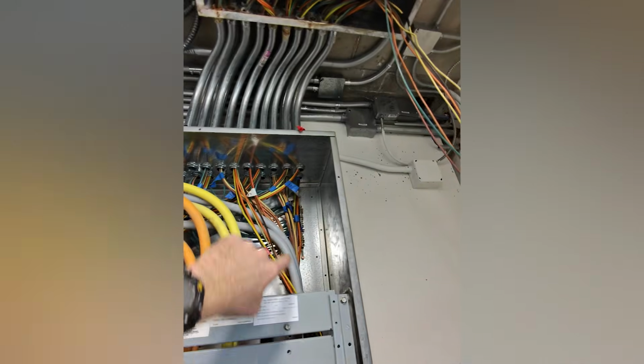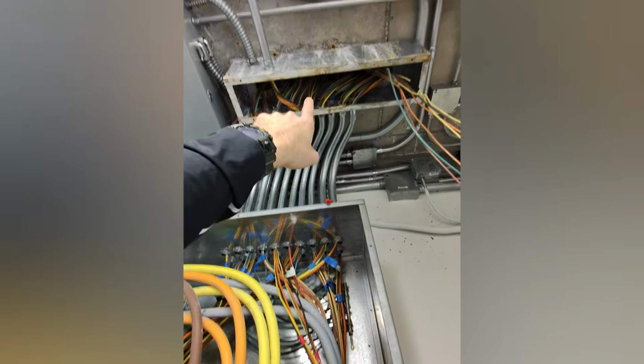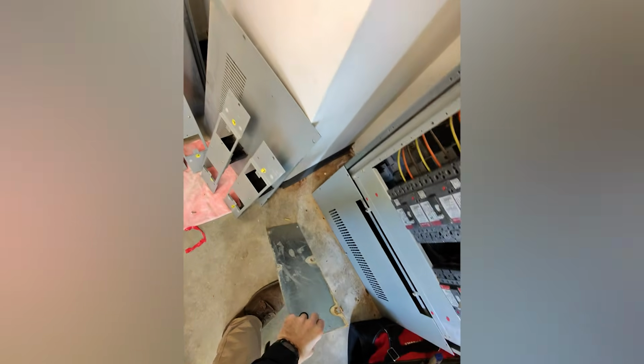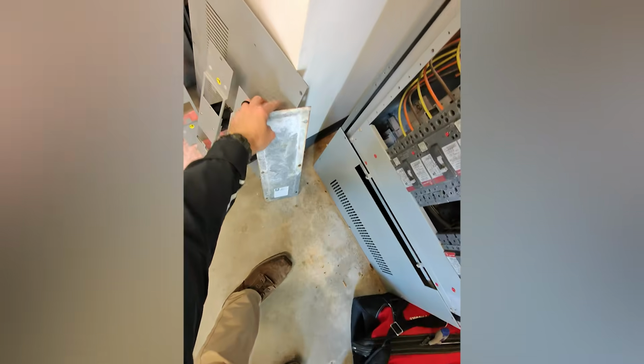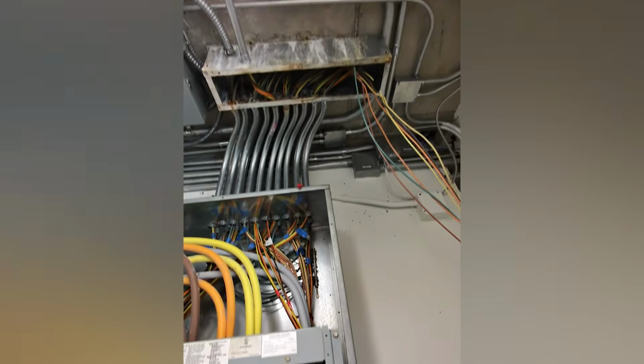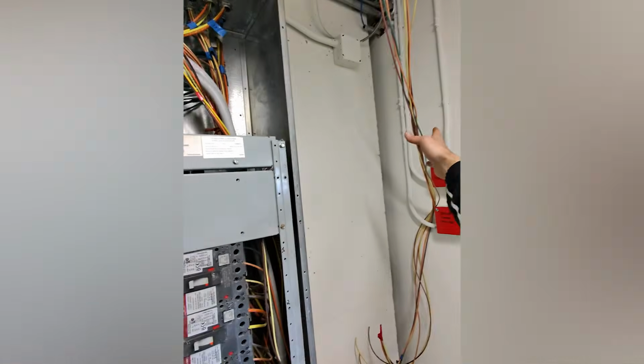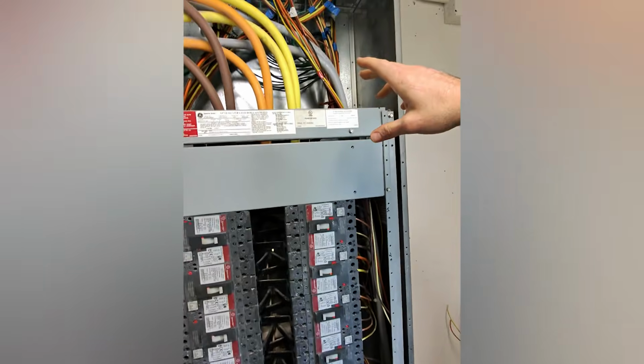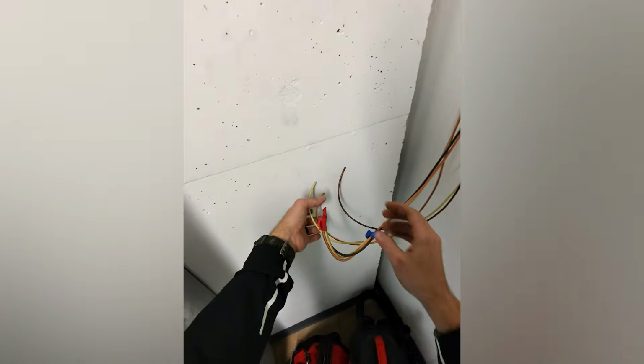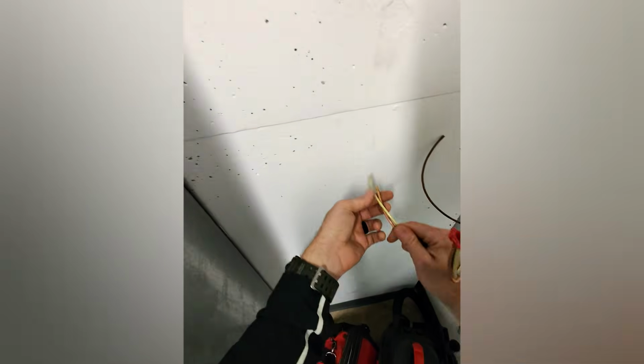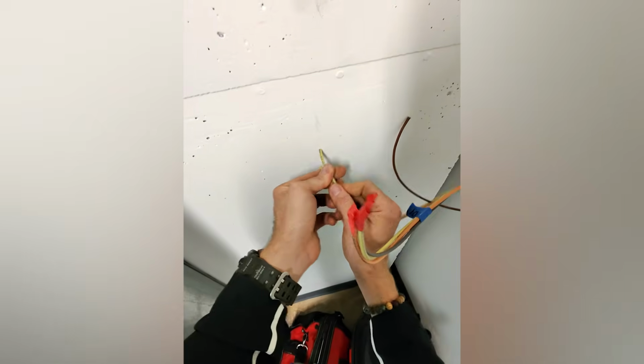wire that goes all the way up and across here into this, and whoa, look at all the rust, the corrosion, a bit of a red flag here. This is the outside, this is the inside. It tells you that it looks like water's been dripping in this panel for quite some time. Here's the crazy wild thing. So the wire coiled up here, extra wires here on the right hand side, actually have water in the wires.